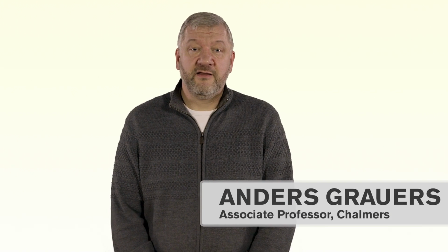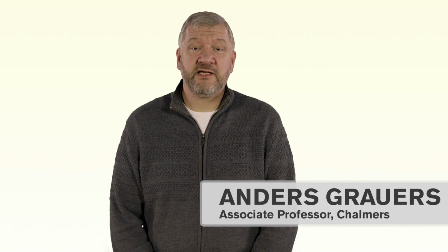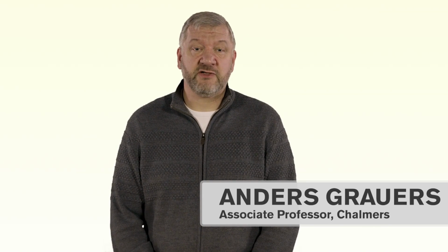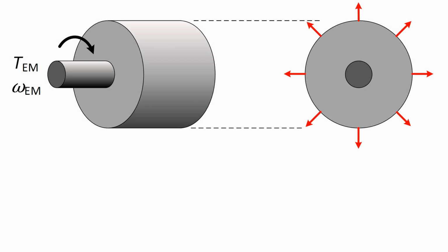Hi again. In this lecture we will look at how the second requirement on the operating range of an electric drive, the maximum speed, will influence the design of the machine and its cost. The speed of an electric machine can often be increased with no changes to the design of the machine except better bearings. The centrifugal forces on the rotor of course increase with speed. At first they have no significant effect, but eventually they become strong enough that the rotor design calls for expensive materials and advanced manufacturing methods.